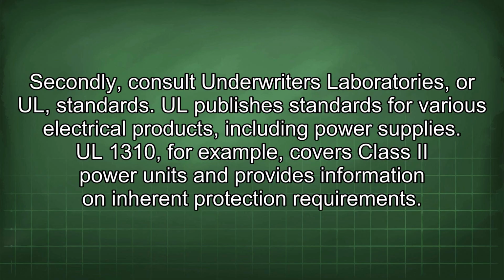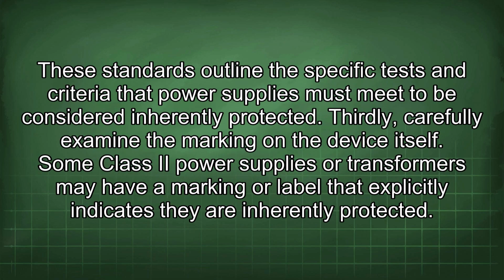Secondly, consult Underwriters Laboratories, or UL, standards. UL publishes standards for various electrical products, including power supplies. UL 1310, for example, covers Class Roman II power units and provides information on inherent protection requirements. These standards outline the specific tests and criteria that power supplies must meet to be considered inherently protected.